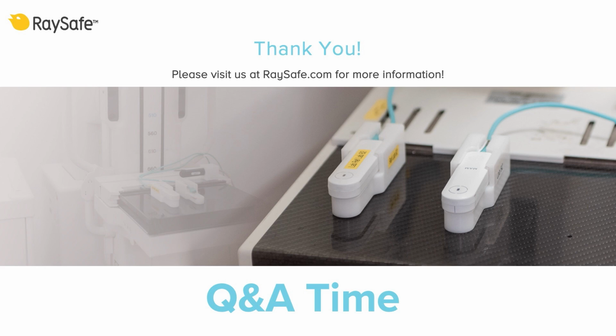Can the 452 be calibrated by an end user? I guess it depends on what you mean by calibration. Calibration, as just looking at the dose rate response, is easy and can be done by a third-party calibration lab. They might even be able to give you a certificate, which is required for some regulations.